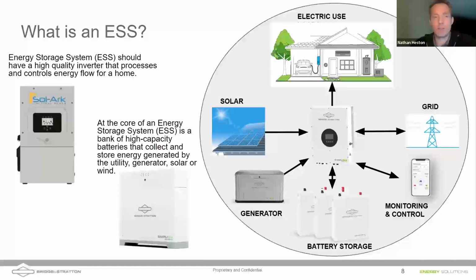So at the heart of an energy storage system is a high-quality inverter. What the inverter does is it processes and controls the energy flow to and from different sources and provides that energy to the home. So you need a high quality inverter that's capable of multiple inputs. The Sol-Ark 15k is an example of a hybrid inverter. It contains MPPTs for taking in solar power, and it contains charge controllers for charging the batteries, as well as transfer switches to switch between the loads to isolate in the case of a grid down event, so that we're not electrifying the lines when the grid goes down, but we maintain continuous access of power to the home.